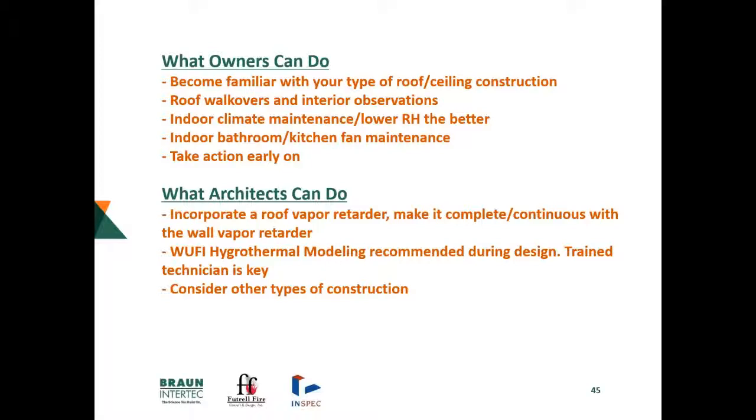So Gary, I've got a couple of questions for you that might be interesting to people. It's sounding kind of like the choice that you and I are coming up with to suggest to people is to put the vapor retarder on top of the deck. Don't worry about what the foam or fiberglass is beneath. You may have to deal with it from a sprinkler, but at least you're not going to get yourself into trouble this way. We're going back to what sort of the old way was, if you will. Correct. That's really what we're seeing is your topside vapor retarder is the place that you can best control that. And if you can make that bridge, we're in successful conditions that way, yes.